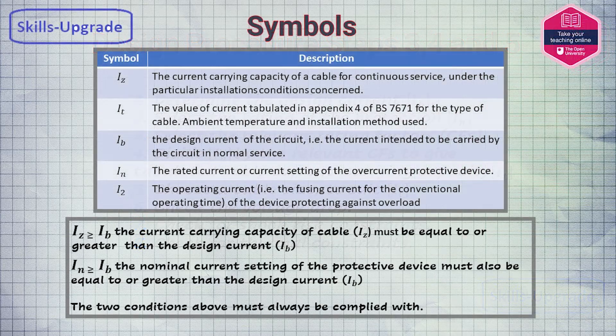There are different definitions regarding current. IZ is the current carrying capacity of a cable for continuous service — the value of current tabulated in Appendix 4 of BS7671 with the type of cable, ambient temperature and the installation method used.